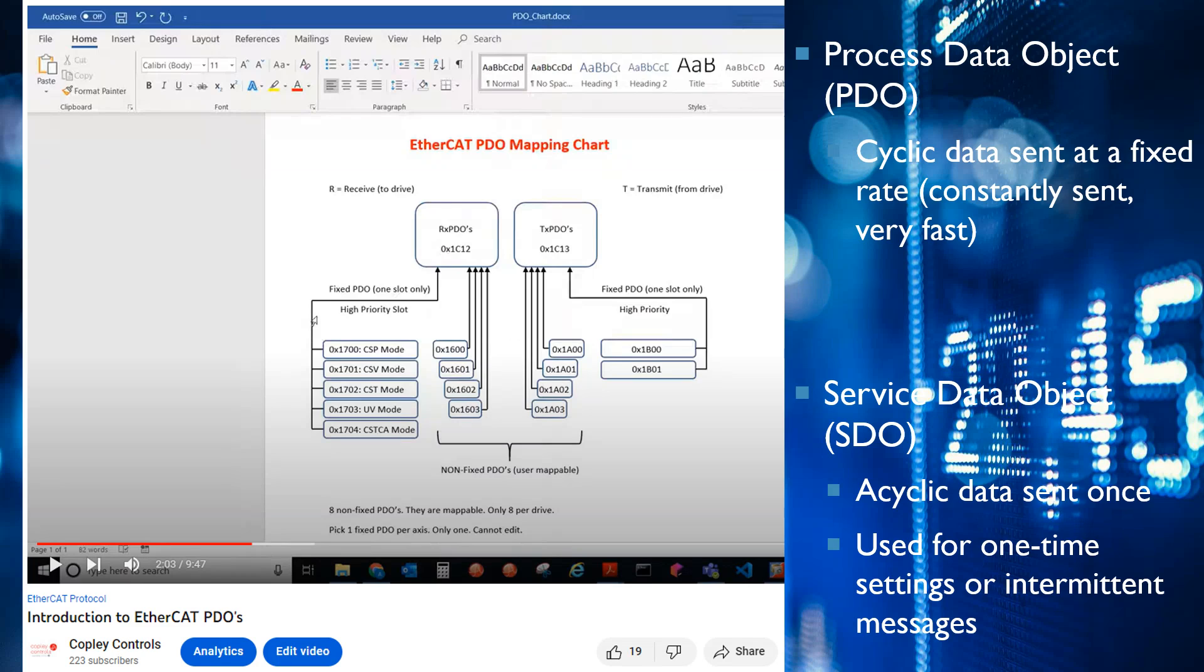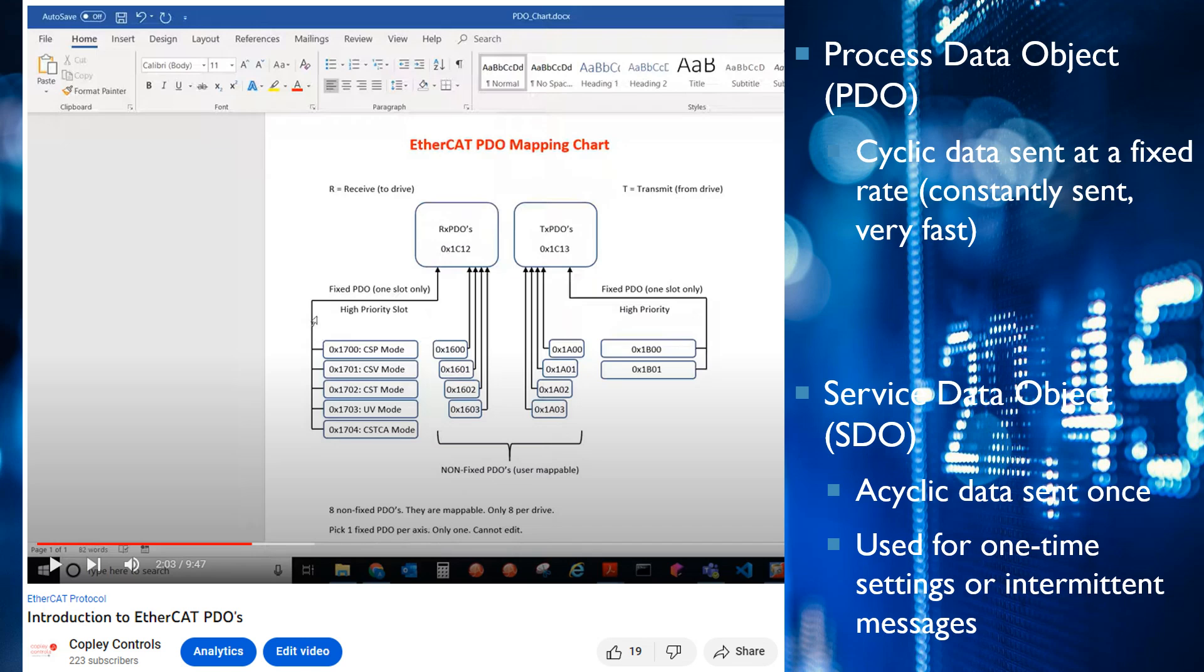A Process Data Object PDO is cyclic data that's sent at a fixed rate, constantly sent, and it's very fast. An SDO object is acyclic data sent once and it's used for one-time settings.